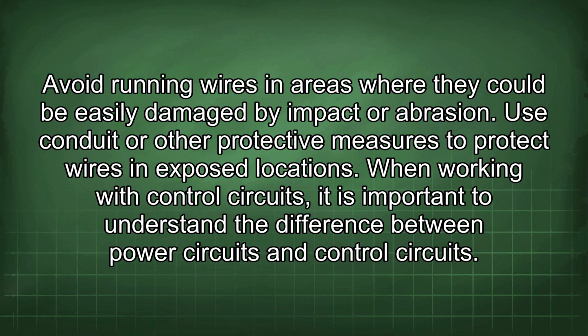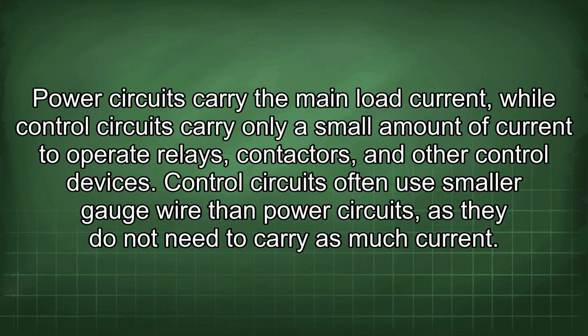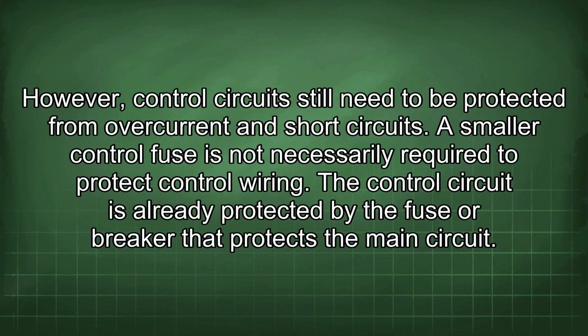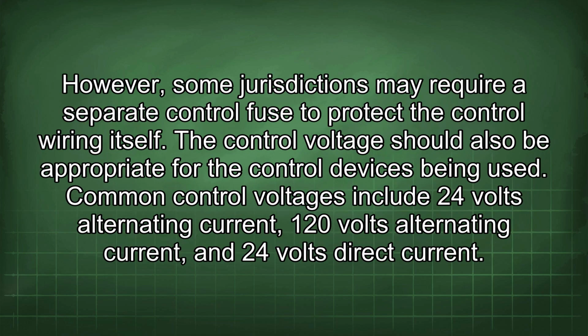When working with control circuits, it is important to understand the difference between power circuits and control circuits. Power circuits carry the main load current, while control circuits carry only a small amount of current to operate relays, contactors, and other control devices. Control circuits often use smaller gauge wire than power circuits, as they do not need to carry as much current. However, control circuits still need to be protected from overcurrent and short circuits. A smaller control fuse is not necessarily required to protect control wiring. The control circuit is already protected by the fuse or breaker that protects the main circuit. However, some jurisdictions may require a separate control fuse to protect the control wiring itself.